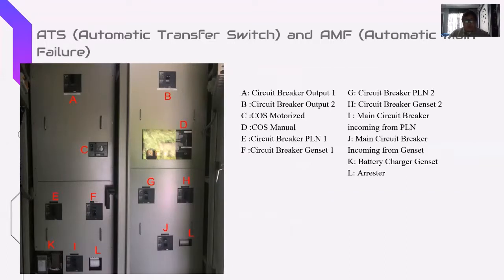main power in a way. They have the circuit breakers. You may notice there are two circuit breakers, for backup, for PLN and genset. Then the choice, motorized and manual. So they have two choices. The motorized is basically an automated version, and the manual is where you manually use the lever to change to the genset.